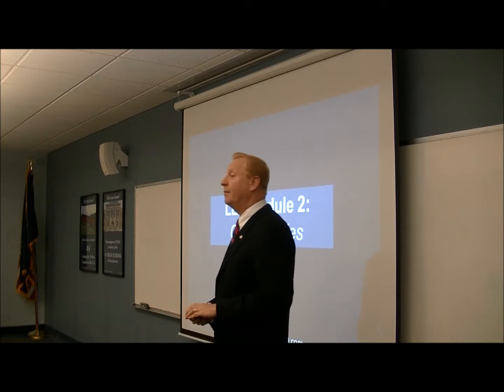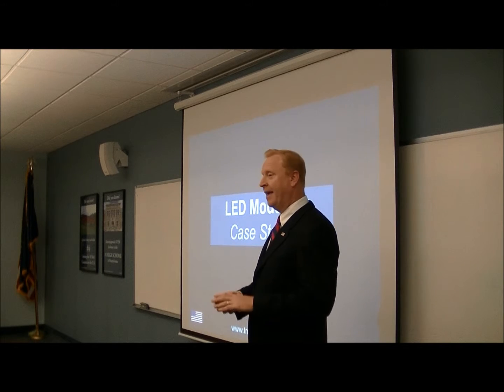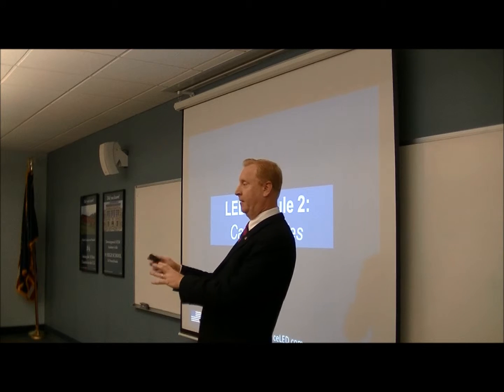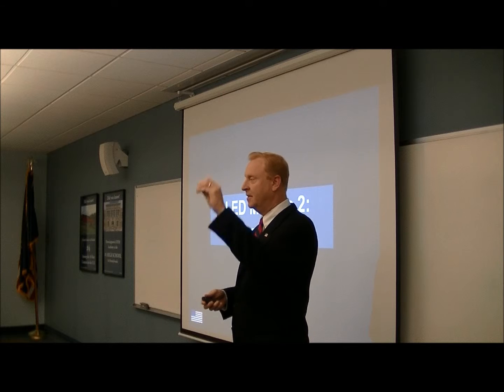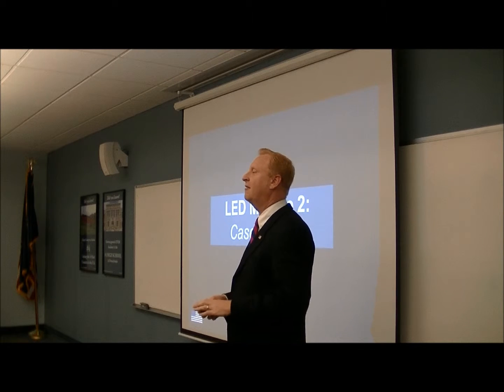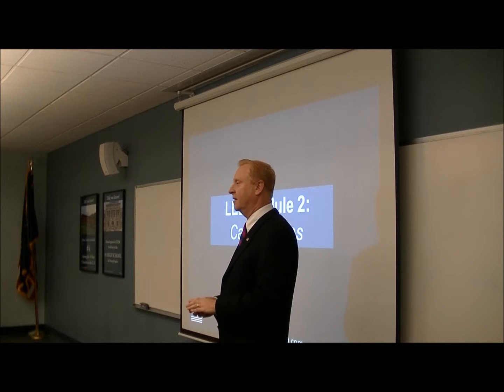Great call. So LM79 is efficiency. That is a test that is required. LM80 is the longevity. Both tests are required to submit for DLC. DLC is checking the box that those tests have been made. They are not doing their own independent testing to verify the findings.